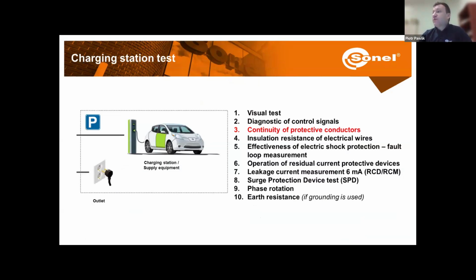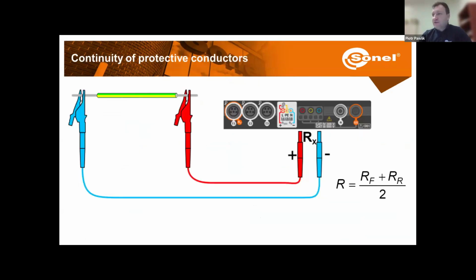Next test, this is the continuity of protective conductors. Basically, this is a pretty easy test. We connect on one end of the conductor, on the other end, and then the meter is going to check the resistance. So it will check the resistance of the test leads together with the part of the wire that we are interested in.